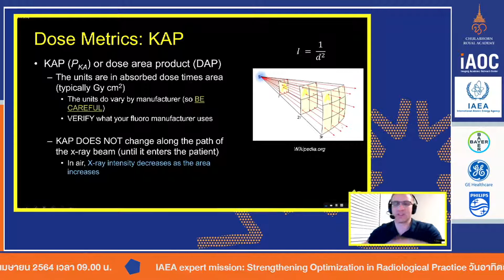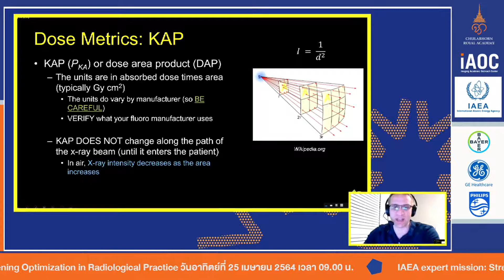Now, once it enters the body, so once it gets to the patient or the fluoro table, whatever object it first impinges on, now you start getting the scatter. And so KAP will change. KAP is not the same inside the body as it is outside the body. And that's why, as I mentioned, it's really hard to use KAP to approximate skin dose or entrance skin dose, I should be more specific.